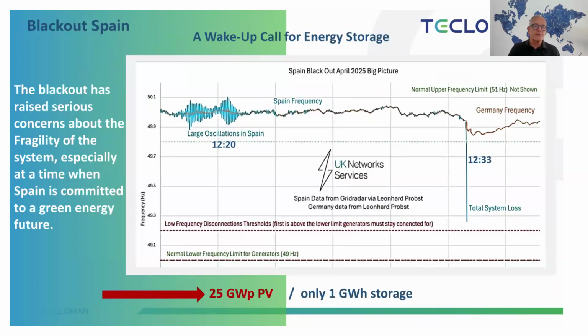The problem causing the blackout was that power plants in Spain got too much power at noontime from the PV, and they couldn't send this power away to the European network because all the countries had the same problem. So too much power occurred in the power stations, and the frequency became unstable. Normally frequency is up to 50 hertz, and you can see they had oscillation problems in Spain — frequency went down mostly to 49 and then eventually to 49.1 hertz. When it drops like that, you get a blackout.